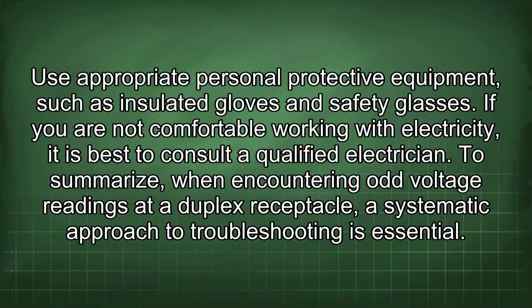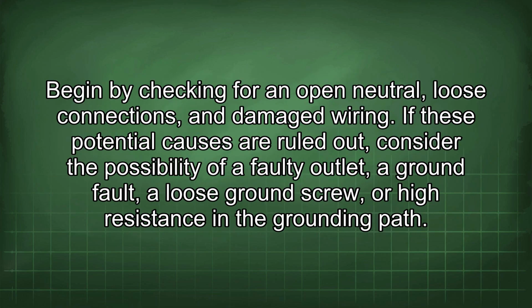To summarize, when encountering odd voltage readings at a duplex receptacle, a systematic approach to troubleshooting is essential. Begin by checking for an open neutral, loose connections, and damaged wiring. If these potential causes are ruled out, consider the possibility of a faulty outlet, a ground fault, a loose ground screw, or high resistance in the grounding path.